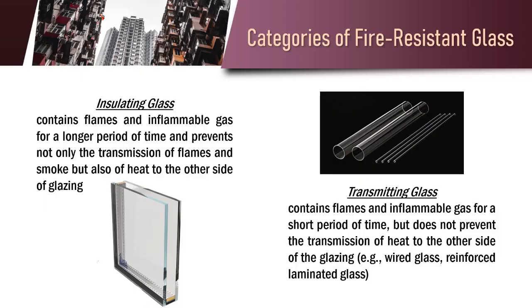There are two categories of fire-resistant glass. First is the insulating glass and the other is the transmitting glass. Insulating glass contains flames and inflammable gas for a longer period of time and prevents not only the transmission of flames and smoke but also of heat to the other side of glazing. On the other hand, transmitting glass contains flames and inflammable gas for a short period of time, but does not prevent the transmission of heat to the other side of the glazing. Examples of this are wired glass and reinforced laminated glass.